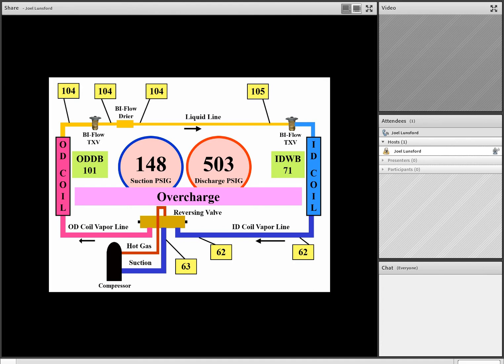And so in our example here, we see we have a gross overcharge with 30 degrees of subcooling on the outdoor coil in the cooling mode and about normal superheat because our expansion valve on the indoor coil is working properly. This is an overcharge with an operating TXV.